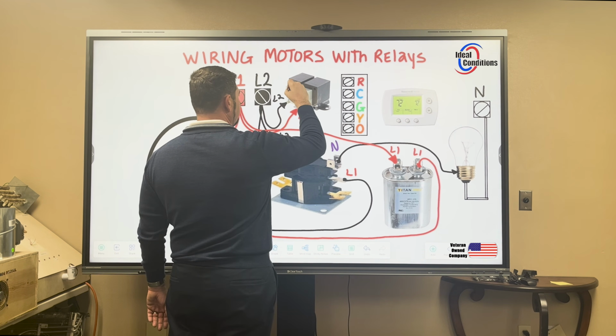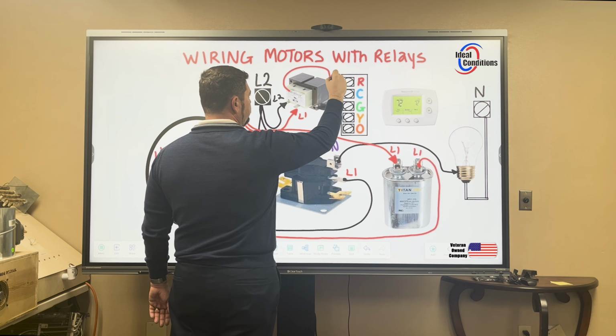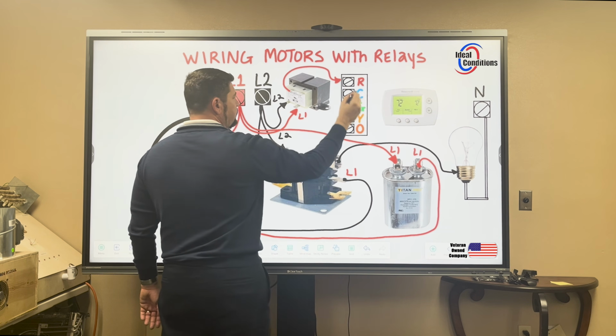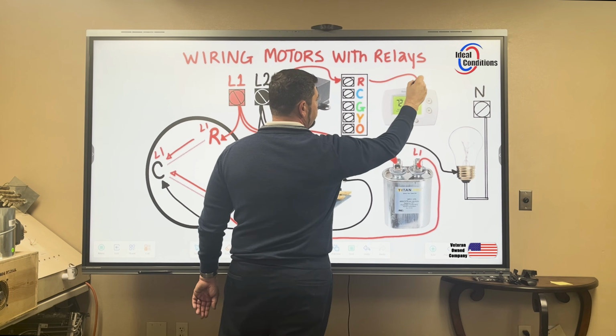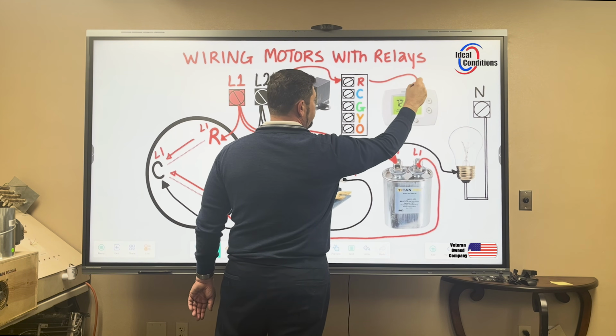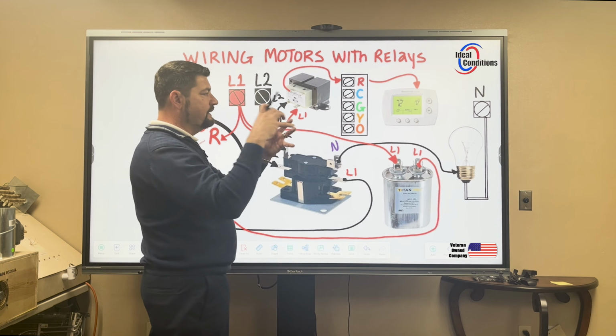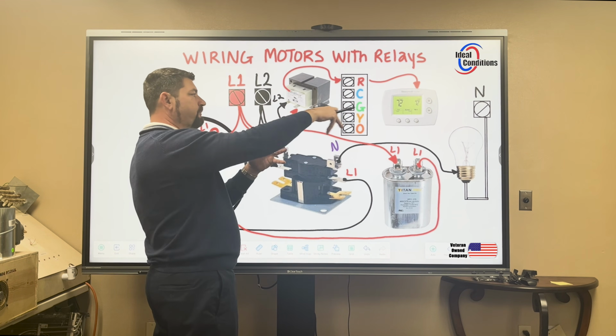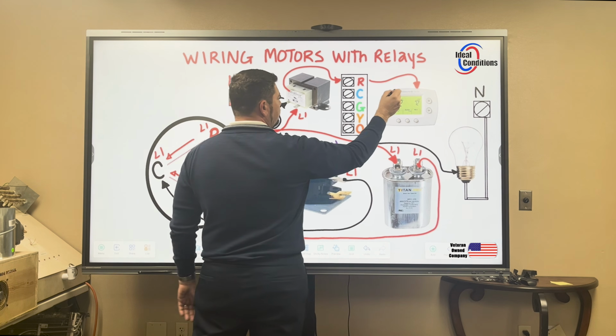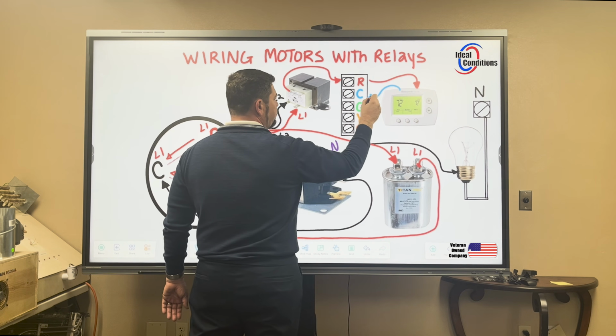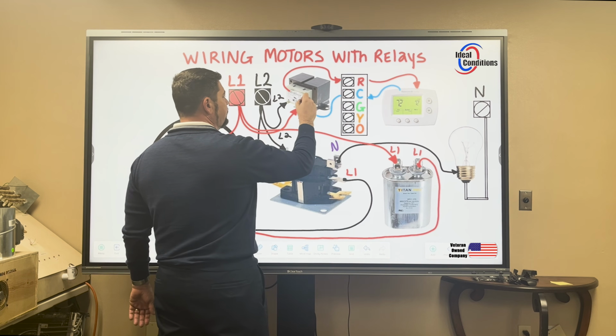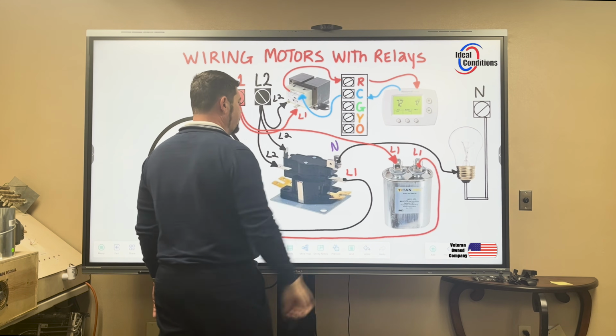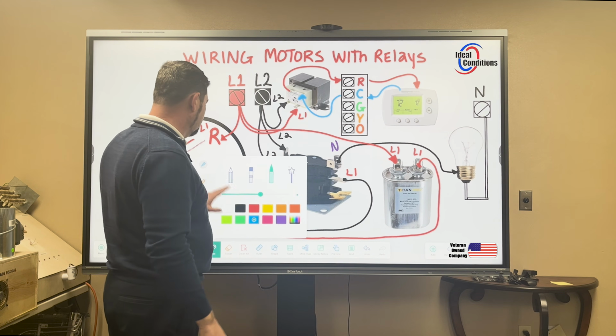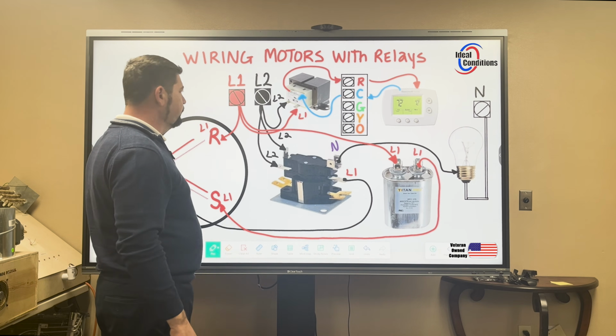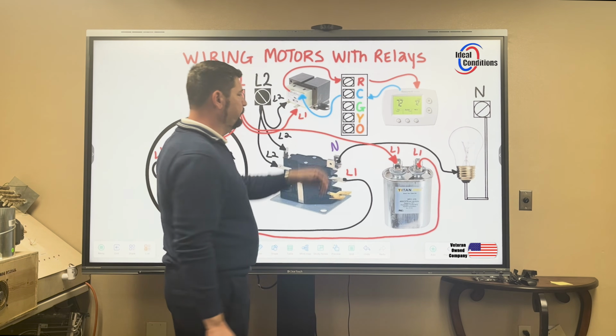We're going to say we have 24 volts coming over to our terminal block. Out of our terminal block, we come over and we feed 24 volts to the base plate of our thermostat. Through the thermostat faceplate, it sends power through the base plate, and then we get back to the transformer, and there's our loop energizing our thermostat, and then we'll start toggling all of our other terminals.